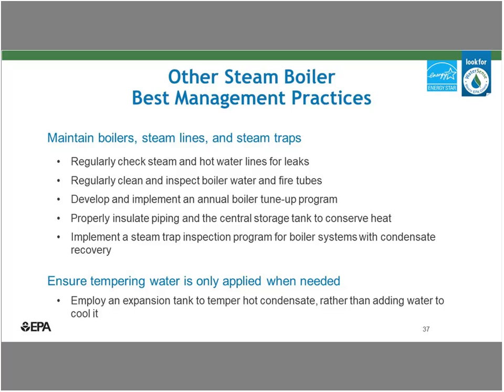And one area that deserves maybe a little bit of careful attention, and that might be looked at as you do rounds within your facility, is the tempering water application. As I mentioned, tempering water is applied when hot water is discharged to the drain. This could be from boiler blowdown, flash tank, or condensate that's draining from the steam vents. These tempering water flows are frequently controlled by a temperature-actuated solenoid valve. If the temperature probe or the valve fails, tempering water can flow all the time, even if it's not needed. As we saw earlier, these types of continuous water flows can be big water wasters, so that's something to try to pay attention to.